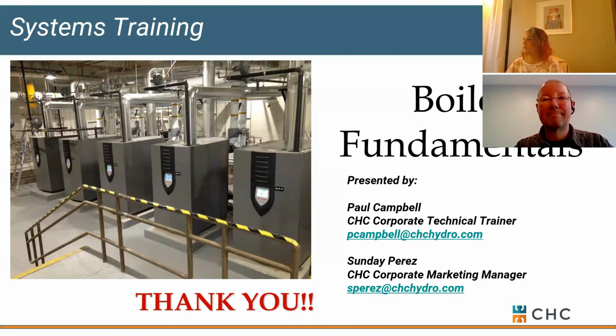Let me get that one. Next question. You talked about the difference between a boiler and a water heater. Can you please also comment on what defines a steam generator? Yeah, I guess I have to be careful with that. So there's steam boilers and a steam generator. We have a clean steam generator, and all that's doing is taking dirty steam from a steam boiler and running it through a coil to boil off RO or DI water to create clean steam. So you've got a boiler and a generator. So I'm not sure how to clarify that much better.